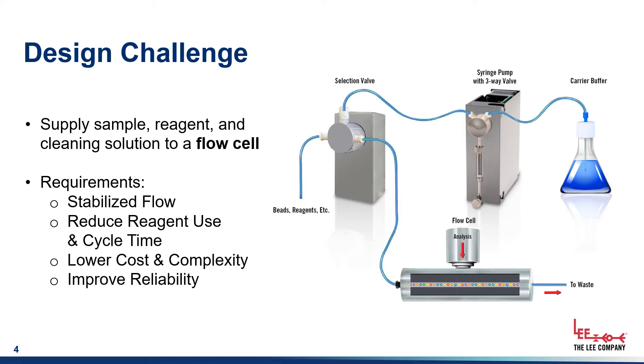Your engineering requirements are first and foremost stabilized flow. You need to make sure that velocity through the flow cell is stable, especially in imaging or sorting applications. Your next objective will be to reduce the amount of expensive reagents consumed and to speed up the analysis time to make your instrument more marketable. Finally, you need to lower the cost and complexity of the system while simultaneously increasing its reliability.